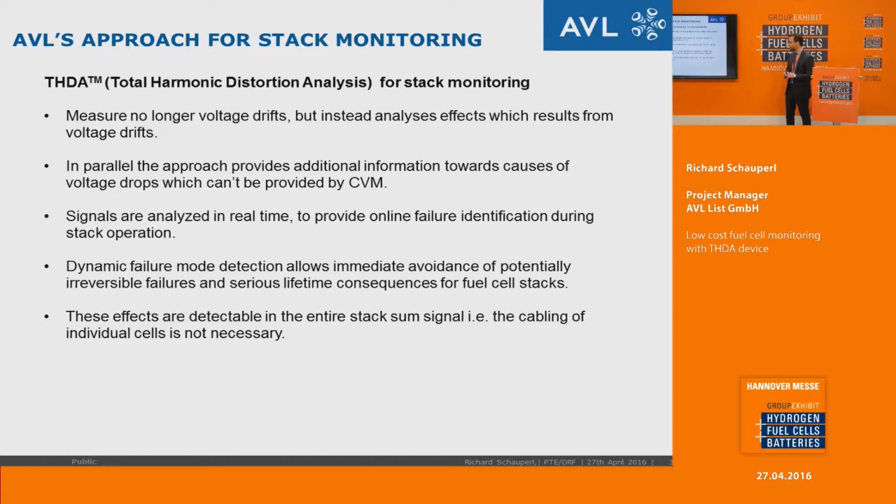We are no longer measuring voltage drifts, we are analyzing the effects of the voltage drifts. This is going on in real time, so it's possible to set immediate counteractions so that the stack will not be damaged. And this is possible with just one wire, taking the entire stack sum signal.